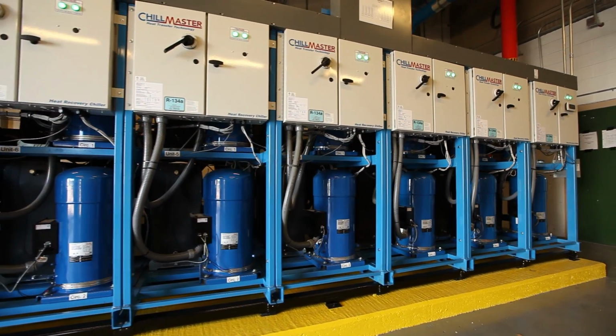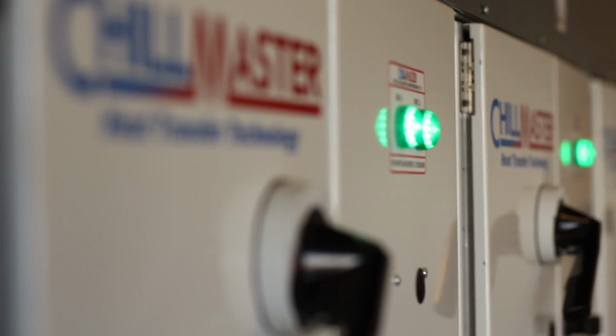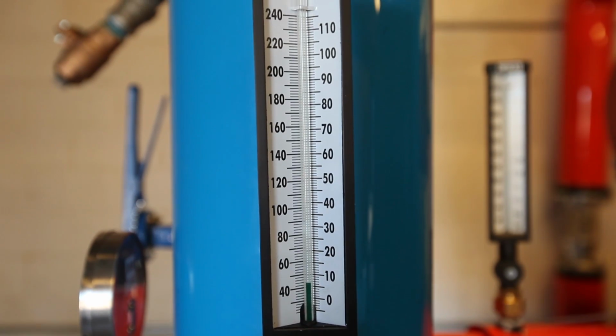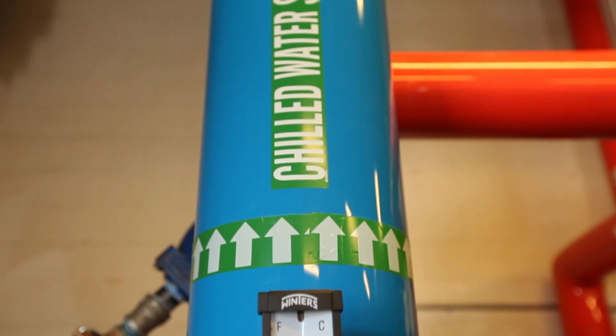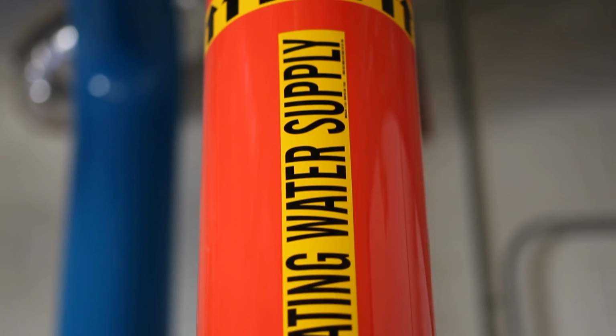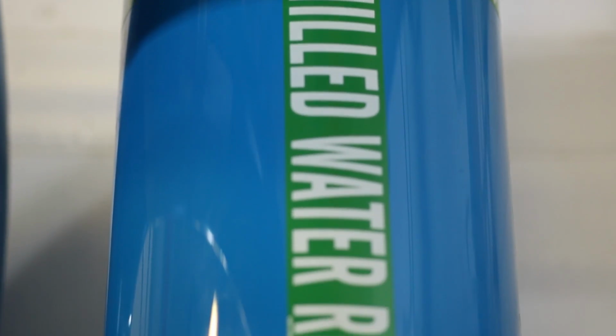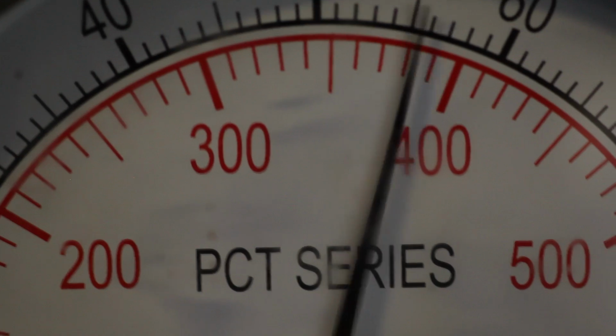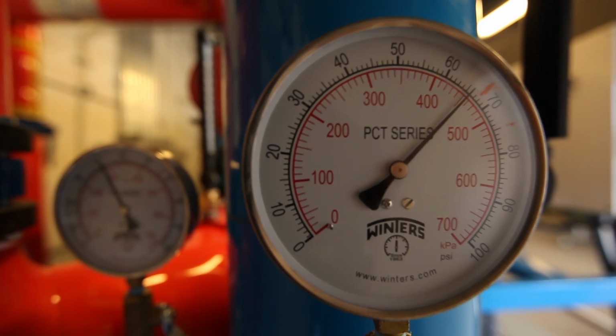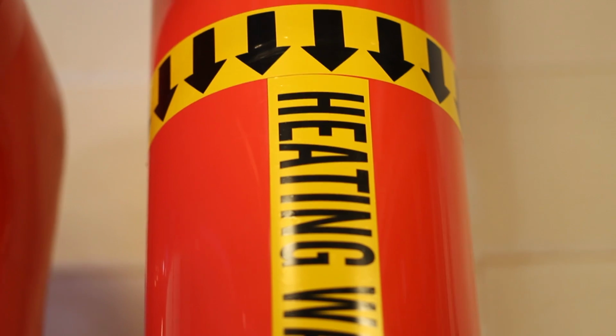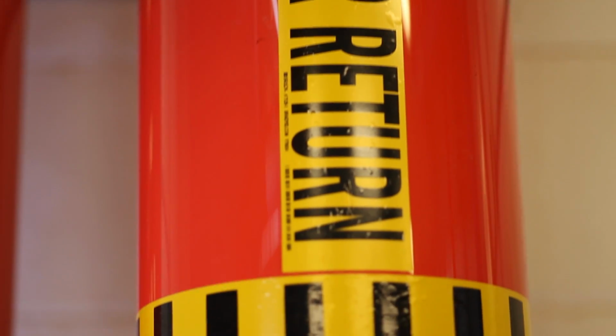The technology involved in the heat recovery chiller program is that we produce chilled water through cooling towers and chillers, which have to be cooled down because of the heat they generate. Part of the process circulates water through a cooling tower, sent from the chiller to the heat recovery chiller. Heat is extracted from that water and sent back to the cooling tower colder than it came. With that extracted heat, we send it through the building to heat the domestic water or the building heating systems. So it's basically a free heat product, using energy you've already spent money on.